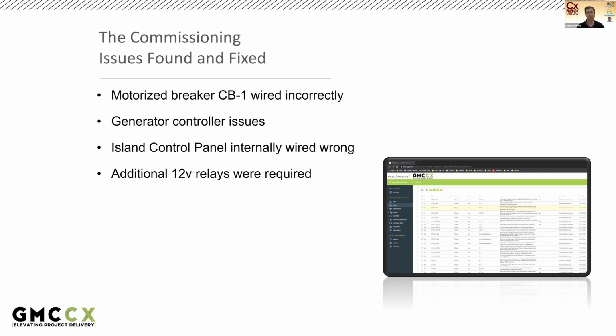The second item was the generator controller issues. The generator was tripping out on reverse power, which means the engine was not producing sufficient torque to keep the generator spinning at its rated speed. So the generator frequency was increased to prevent trip off when paralleled with the battery and with solar.